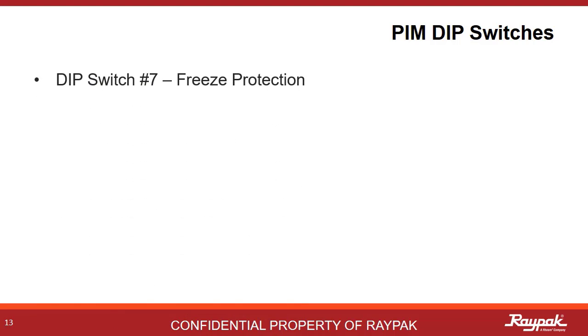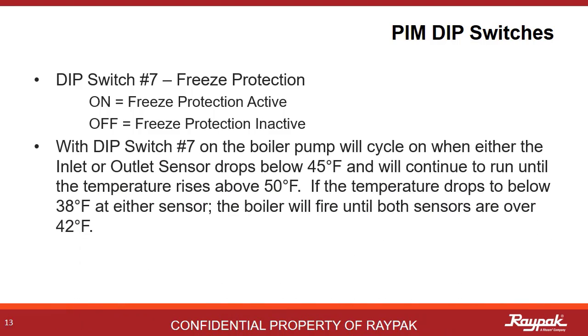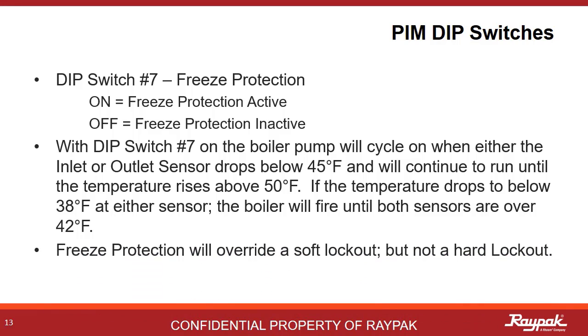Dip switch number seven is another example of some cool Raypak engineering. Turning on number seven enables freeze protection for the boiler. If the temperature drops below 45 degrees at either the inlet or the outlet sensor, then the boiler pump will run for a bit, drawing some heat from other areas in the system until the temperature is higher than 50 degrees at both sensors. If the temperature continues to drop and gets below 38 degrees at either sensor, then the boiler will fire for a few minutes until both sensors are over 42 degrees Fahrenheit. This process will override a soft lockout, but not a hard lockout as that would be dangerous.